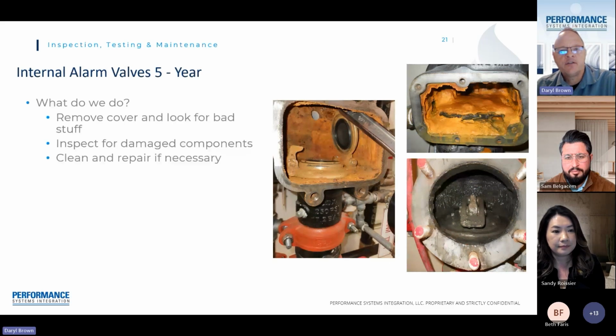These are some of the items that we find during an internal valve inspection. As we showed you on that first picture, some of the valve components. There on the left, you can see it's a pretty clean valve, not a lot of blockage. There on the right, on the top, these are some actual items of what we've found inside fire sprinkler piping. So now you can imagine if that fire sprinkler system does activate, that can clog sprinkler heads or prevent that valve from opening completely. There at the bottom right, that's a clean valve. So that little piece actually opens up as water starts to flow through the system. So if there's significant corrosion or mechanical damage, water will not flow through the system. So that's what we look at every 5th year.